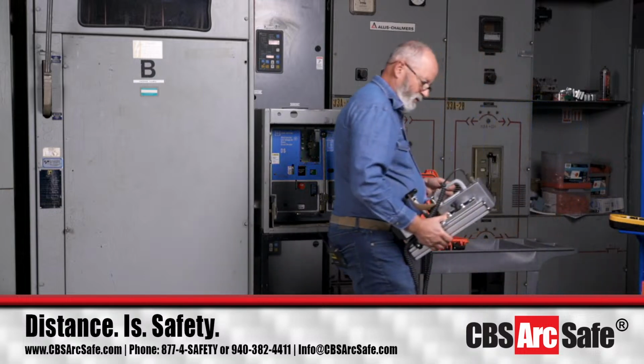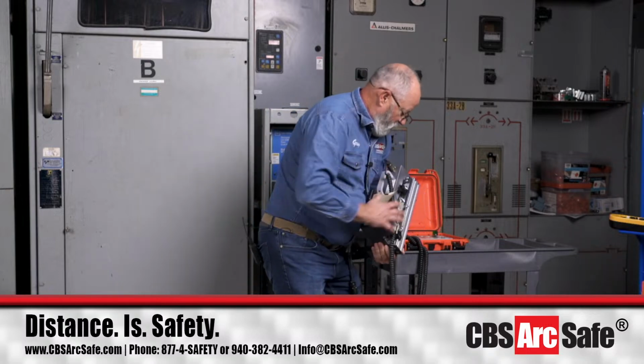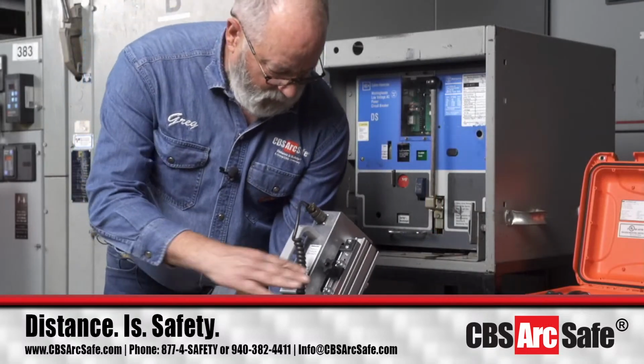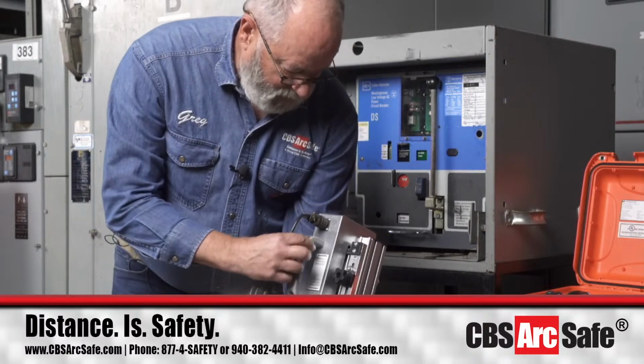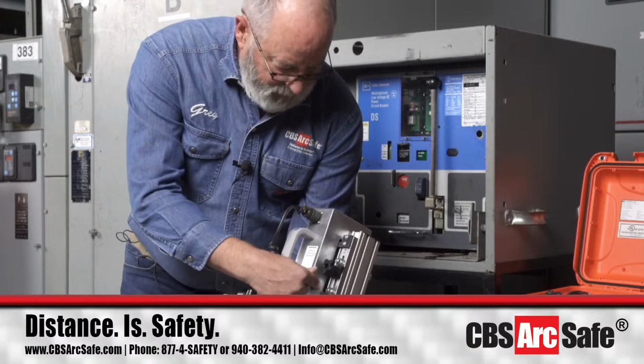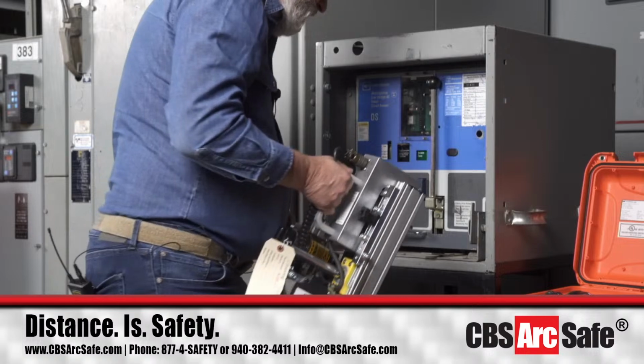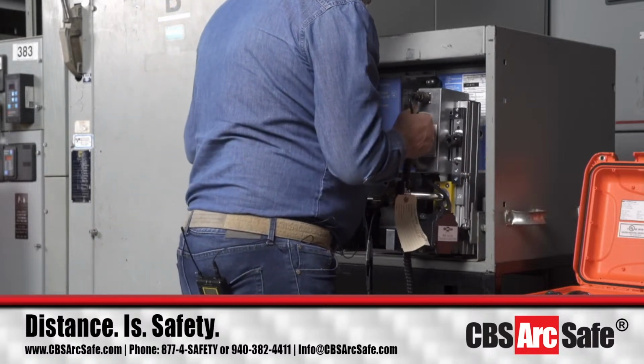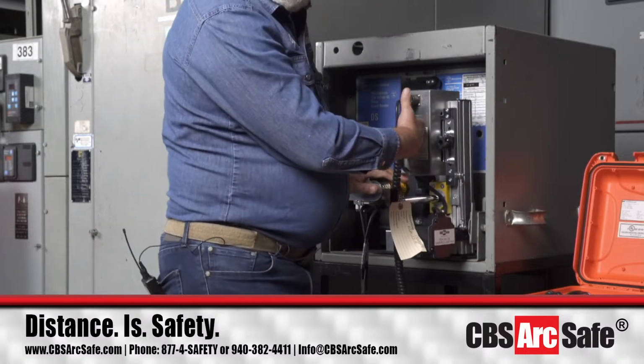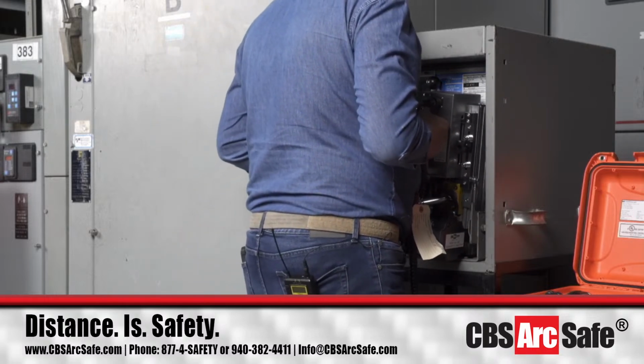And this is made, if you look closely at it, I'm going to show it on this picture over here, Brian. I'll show it on this one. It says manual and electrical. And so I can just move this, and it'll change the position switches internal into the RSA for being able to actually do either the electrically operated breakers or the manually operated breakers.